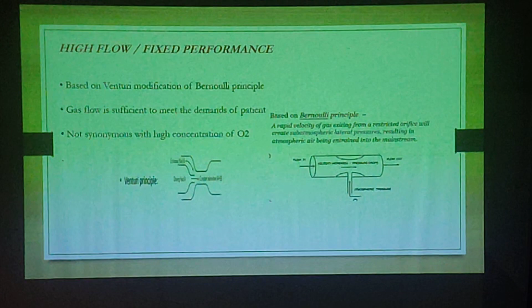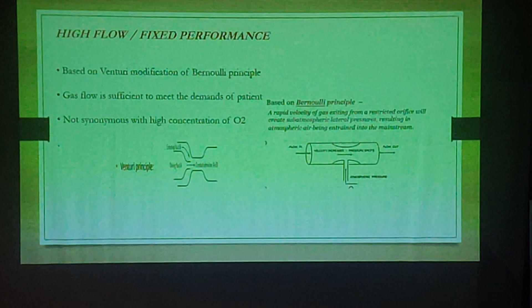These are the Venturi masks, based on the Venturi modification of the Bernoulli principle. In this, there is a narrow inlet in the mask. Through that narrow inlet, a very high flow of oxygen enters the airway, the nose or the mouth, and when this oxygen passes through the narrow inlet, a low pressure system is created outside that inlet. So from outside there is entrainment of air, and that is how the fixed delivery of oxygen is maintained.